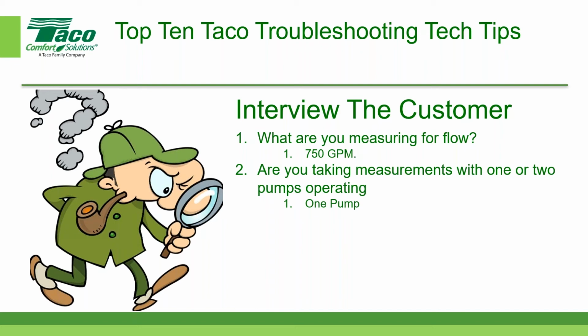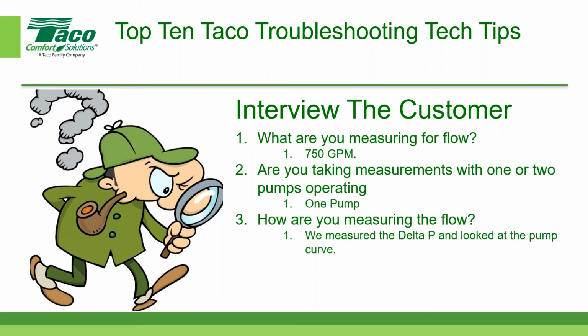So they took the measurements on 1 pump, so that was a good thing. So now we know the data they've given me so far is 750 gallons per minute, and there's 1 pump operating. Okay, so the next key question is, how are you measuring the flow? And you know, the preferred method is usually a calibrated flow meter that is either permanently installed in the piping system or it's a non-invasive flow meter, like a strap-on flow meter, ultrasonic flow meter, or something on that scale. In this particular case, however, the customer came back and said, well, we measured the delta P and we looked at the pump curve. Well, that gives us an indication perhaps of what's going on, but it doesn't necessarily tell us that that's actually what the flow is. But we put that in our basket of information that we've collected.